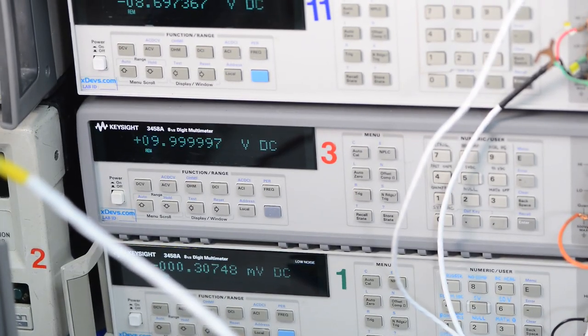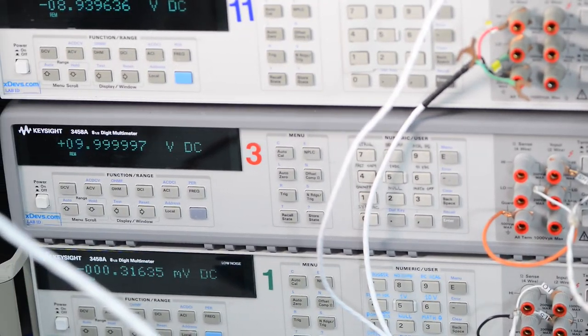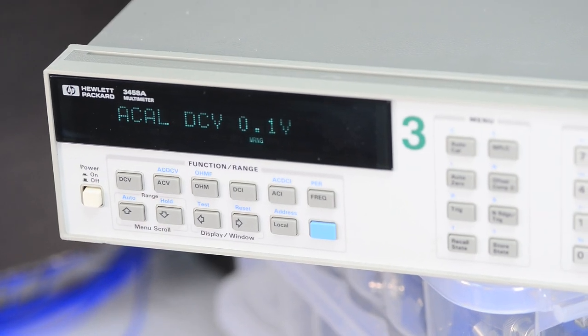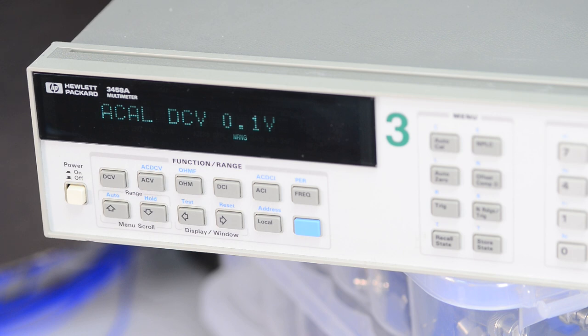And just to make sure, I have the same voltage connected to my reference 3458A, which indeed shows 10 volts. During the ACAL procedure, the instrument tests all the functions and ranges, and using the known voltage from the A9 reference, written down in constant CAL 2-1, it uses that voltage to calculate all the new gains and ratios. That automatically adjusts all the readings to meet the requirements and specifications of the 3458A. That is, given that all the transfers and linearity of the A3 board are good. So that is actually the question that we're going to test in this A3 board after this baking and reassembly procedure. I've selected only to run ACAL DCV, so it would not adjust resistance or AC functions.